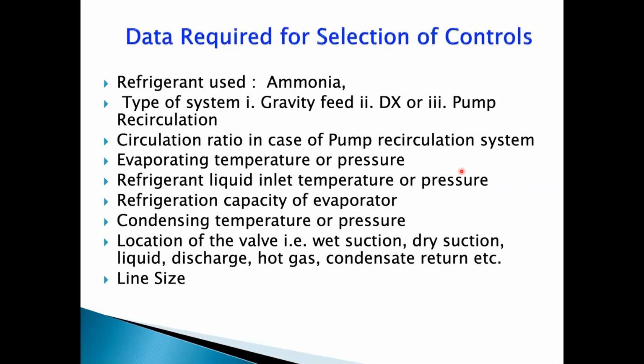So what data do we need when we are selecting these controls? We need to understand the refrigerant used, the type of the system, whether it's gravity feed, direct expansion, or liquid overfeed pump recirculation. In case of pump recirculation, because we are circulating a higher capacity of liquid, we must understand the recirculation ratio, the evaporating temperatures, the pressures in that particular evaporator, and location-wise the refrigerant inlet temperatures, condensing temperatures, and capacity of individual evaporators. These are just the parameters I'm trying to share, but we will see more and more of this when we go into the control parts.